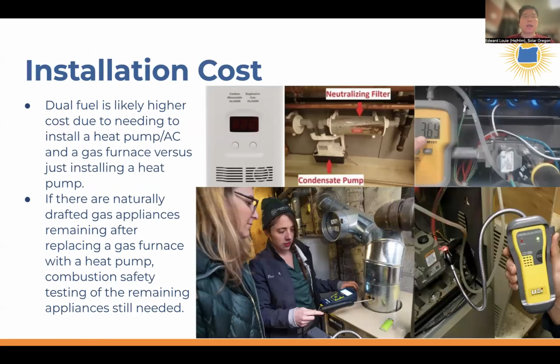On the install cost side, having a dual fuel heat pump likely will result in some higher cost of installation, and that's because the installer needs to not only install the heat pump side, they also need to install the gas stuff, which would entail calibrating the gas valve in the gas furnace based on the gas pressure from the gas meter. And then, of course, all the gas connections need to be checked for leaks. The combustion of natural gas needs to be vented to the outside, and so there needs to be a test of the ventilation or the vent of the gas system, and so time and resources need to be expended to do those types of tests.